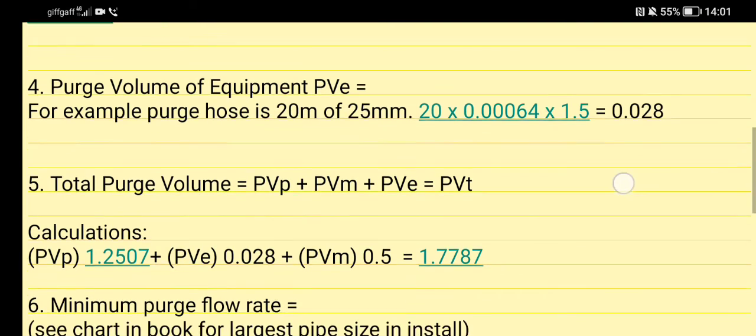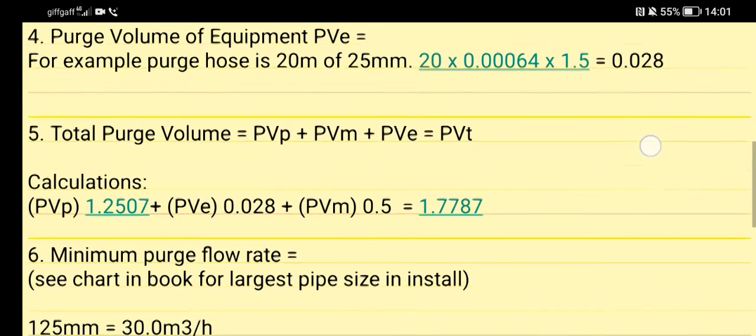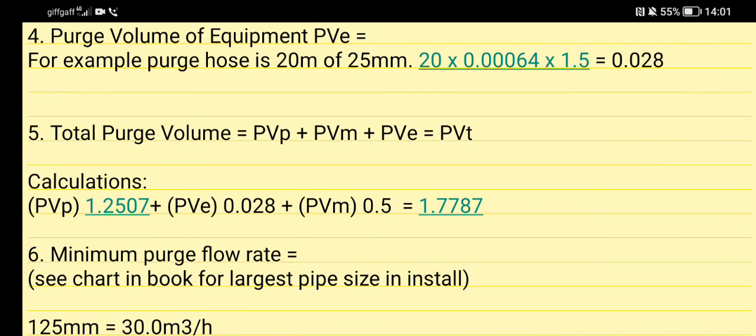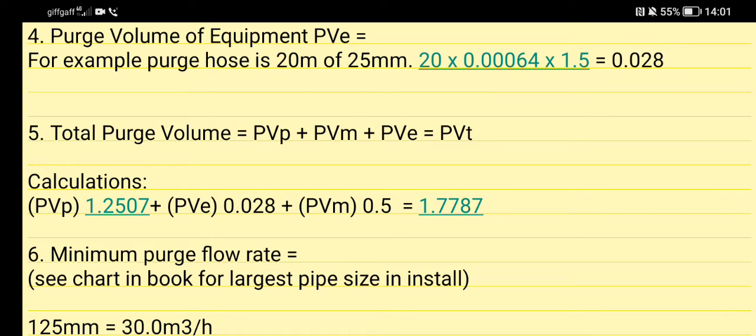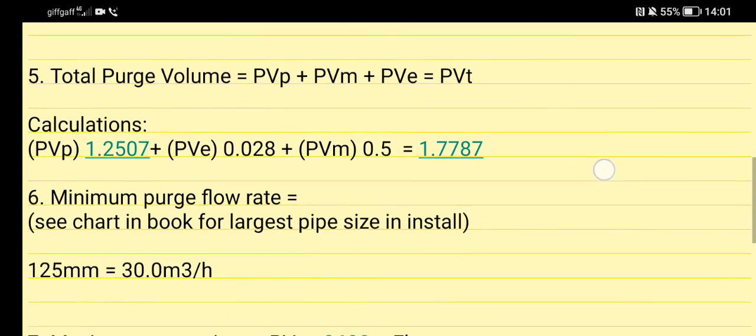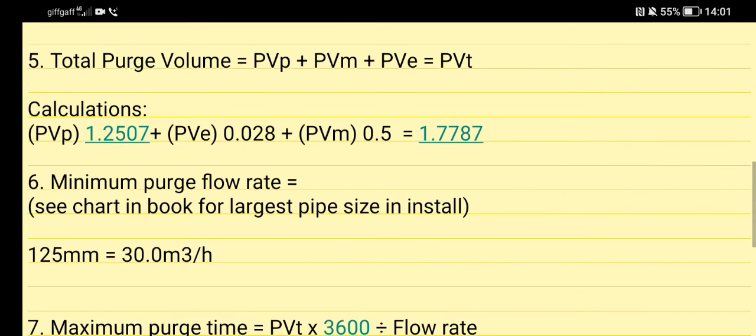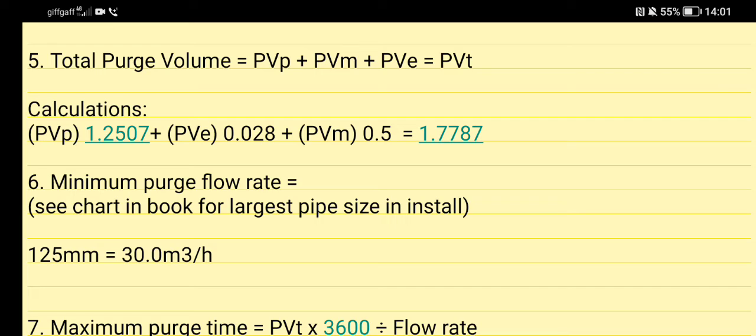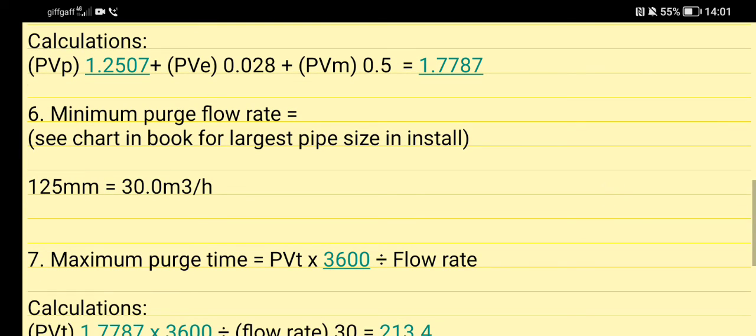Then moving on, now that we've got our answer, we need our total purge volume. That's PVP plus PVM plus PVE - that gives us our PVT, our total purge volume. So here it is: PVP 1.2507 plus PVE which is 0.028 plus PVM which is 0.5 equals 1.7787.